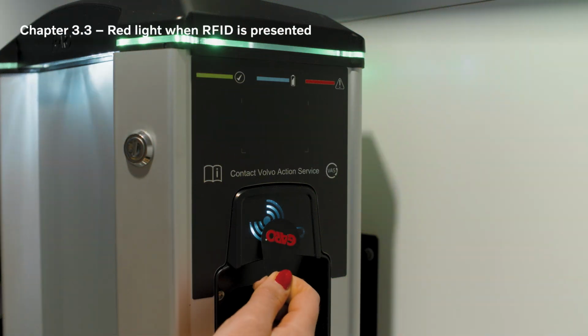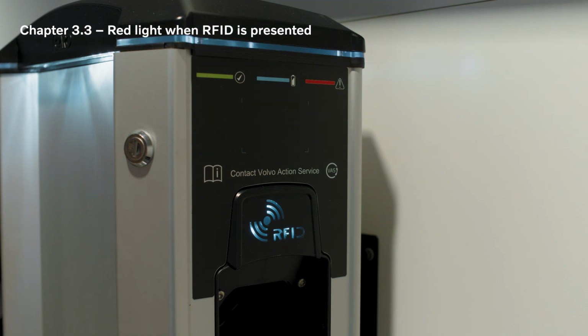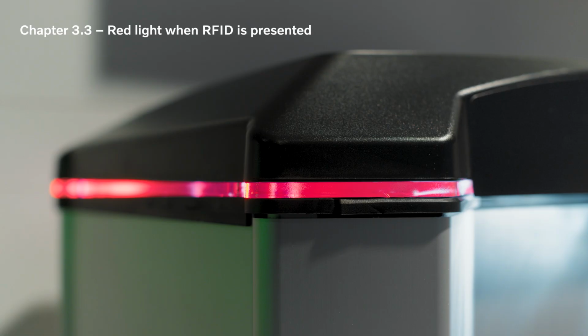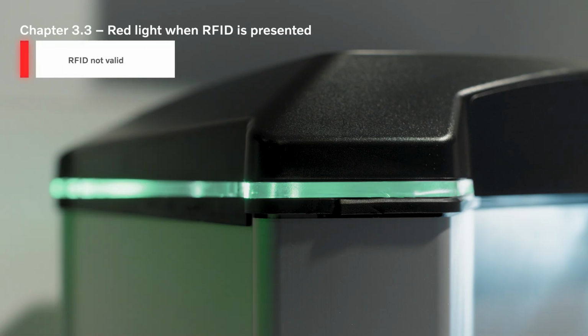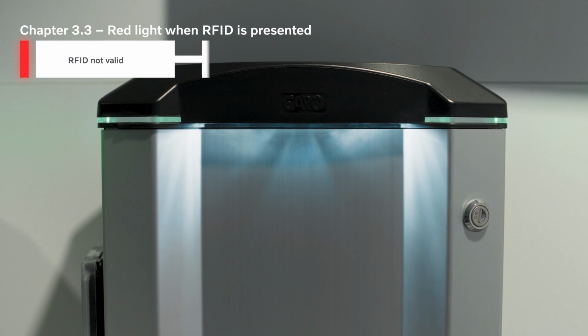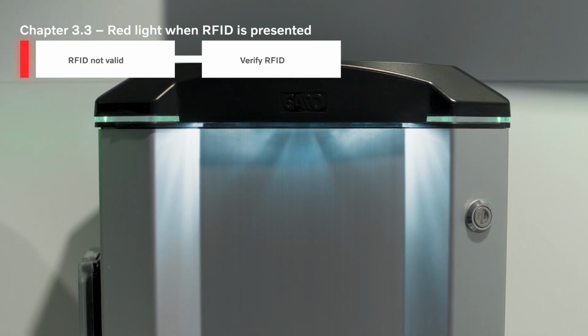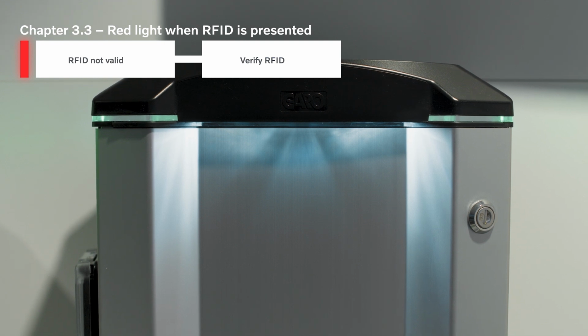If a firm red light appears for 3 seconds when you present your RFID device, it indicates that the RFID isn't valid or hasn't been approved in the back end. Contact the support to verify that the RFID card or tag is approved by the backend.